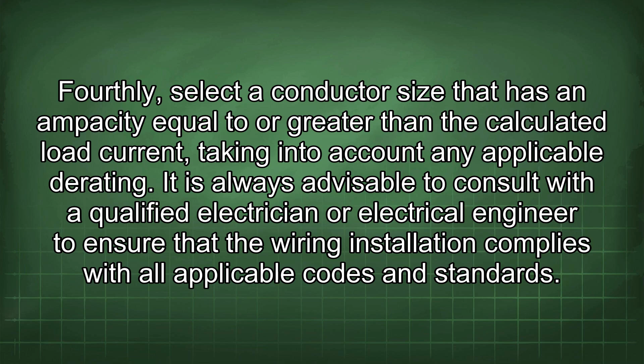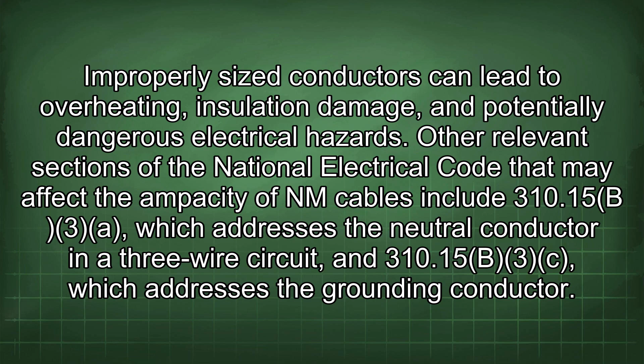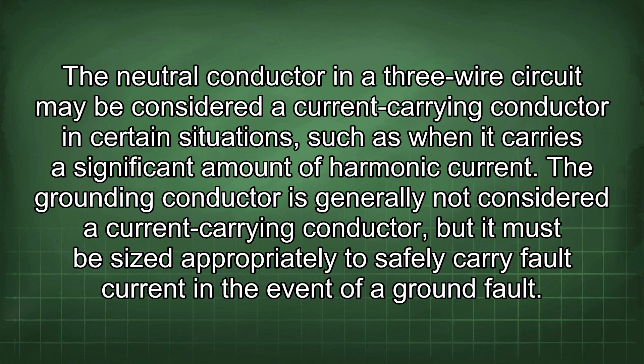Other relevant sections of the National Electrical Code that may affect the ampacity of NM cables include 310.15(B)(3)(a), which addresses the neutral conductor in a 3-wire circuit, and 310.15(B)(3)(c), which addresses the grounding conductor. The neutral conductor in a 3-wire circuit may be considered a current-carrying conductor in certain situations, such as where it carries a significant amount of harmonic current. The grounding conductor is generally not considered a current-carrying conductor, but it must be sized appropriately to safely carry fault current in the event of a ground fault.